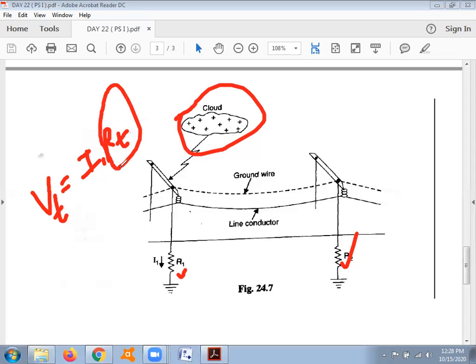In this concept, the overcurrent flows through the ground wire. A limitation is that if the ground wire breaks due to excessive current, it may short to the line conductor, resulting in a short circuit fault. To overcome this, galvanized steel wire is used as the ground wire. The advantage is that it can protect line conductors from overcurrents by taking all the discharge from the cloud to itself and then discharging through the tower body to the ground via low footing resistance.